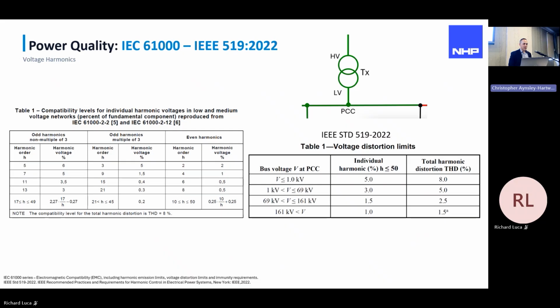With the IEC 61000 standard, under voltage harmonics, the limits are 8% for the facility. That's in IEEE 519. But that's at the PCC, the point of common coupling, where the low voltage side of the transformer utility connects to the consumer's load, generally the main switchboard.